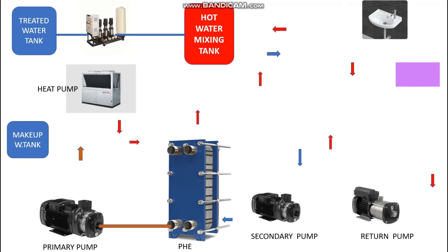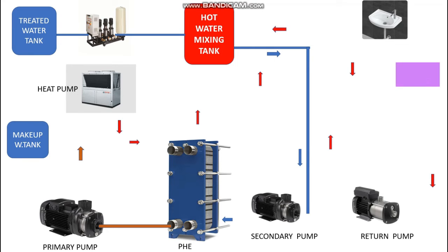This can be done with the help of the PHE — the plate heat exchanger. The secondary pump takes the cold water from the hot water mixing tank. This cold water comes out from the tank and goes to the secondary pump. The secondary pump pulls the cold water from the hot water mixing tank, and from the discharge of the secondary pump it feeds to the inlet of the PHE on the cold side.